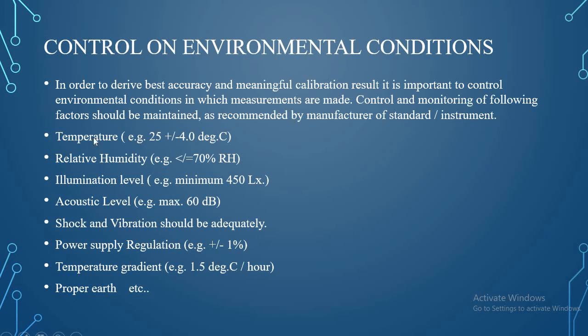So, we have to maintain the temperature which is recommended by the manufacturer of that instrument or standard. Then we have to maintain relative humidity also. We have to maintain the illumination level while the calibration process is going on. We also have to maintain the acoustic level. Then shock and vibration should be adequately maintained. Power supply regulation, that is, there should not be variation in power supply while we are conducting the calibration of any equipment or instrument. Then temperature gradient. Then proper earthing should be there for the instruments where it is necessary while doing the calibration.